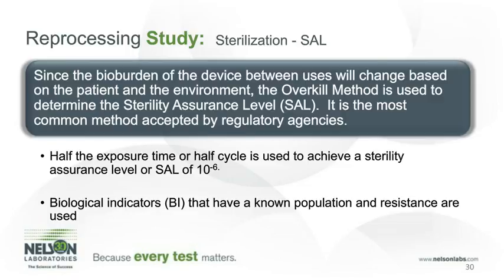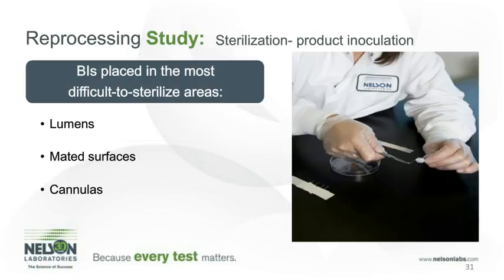Biological indicators are placed in the most difficult to sterilize areas. These include lumens, mated surfaces, and cannulas. In a tray that is utilized for, say, a hip replacement surgery, we may have up to 20 to 25 different types of biological indicators in spots that are most difficult to sterilize, to ensure that everything in the whole entire case is sterilized appropriately.